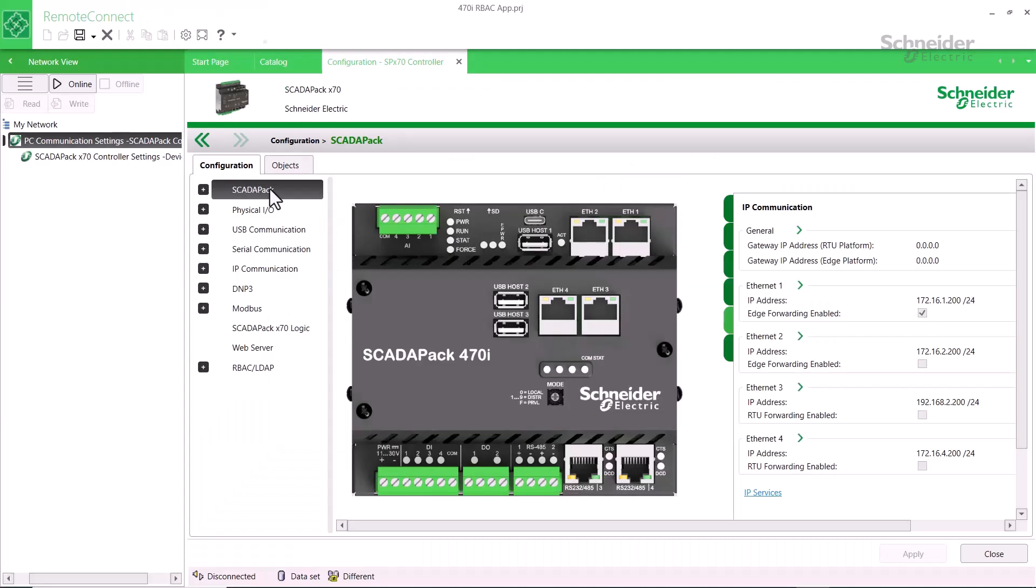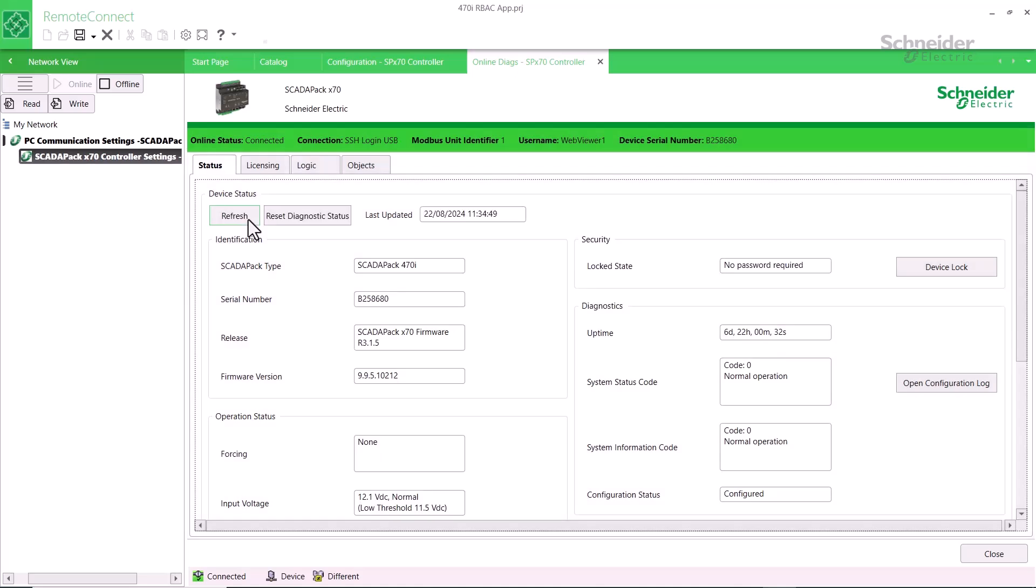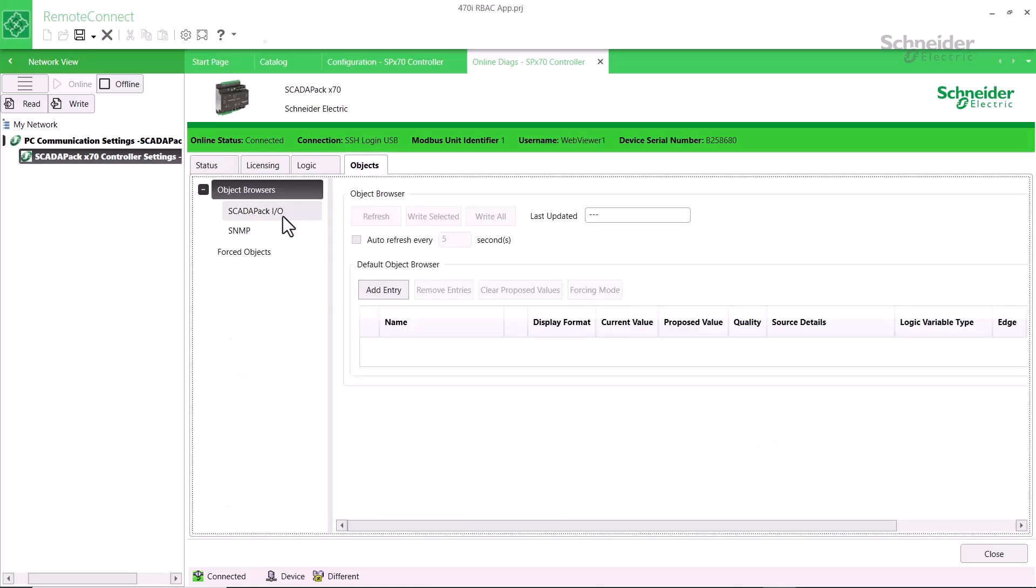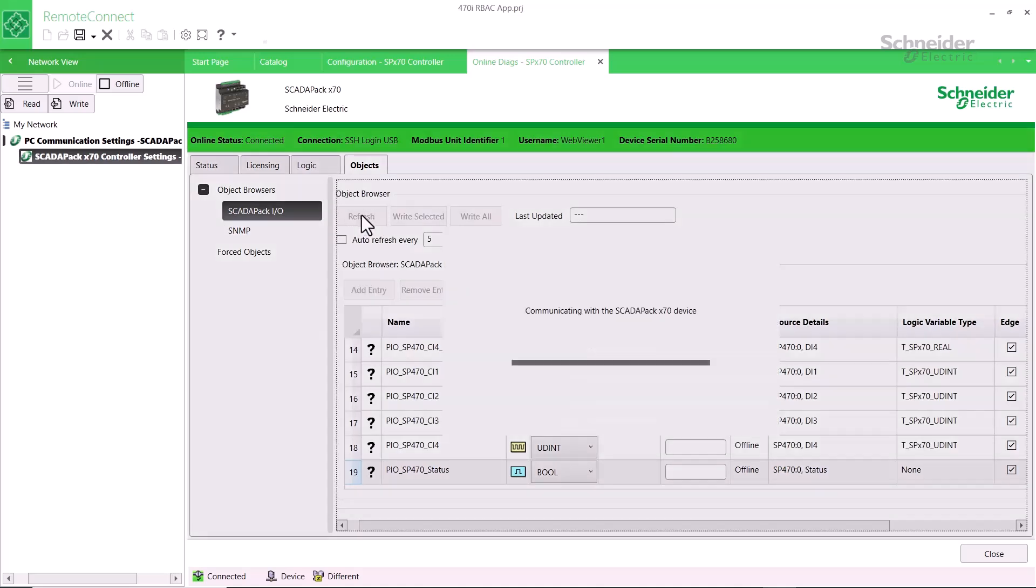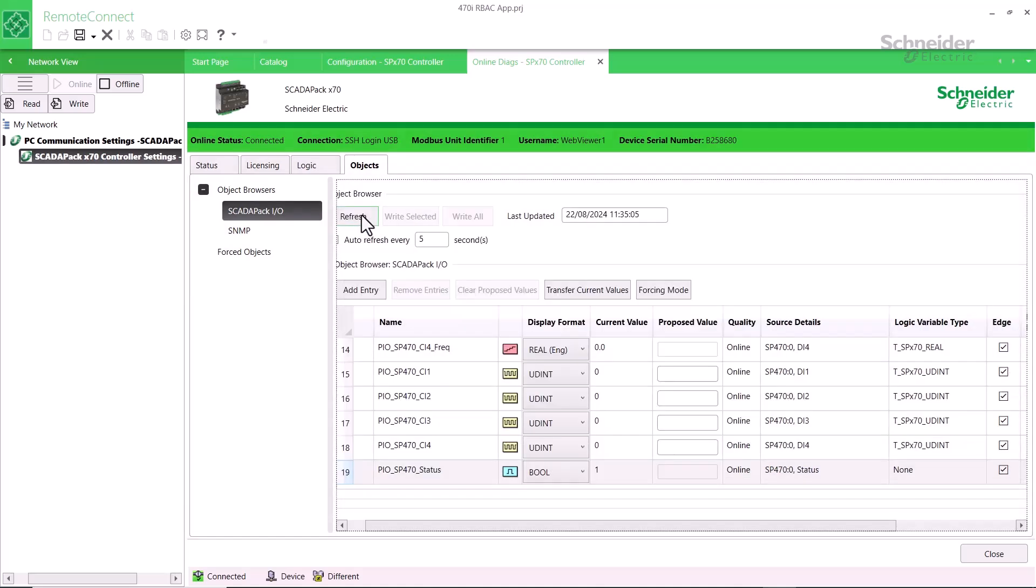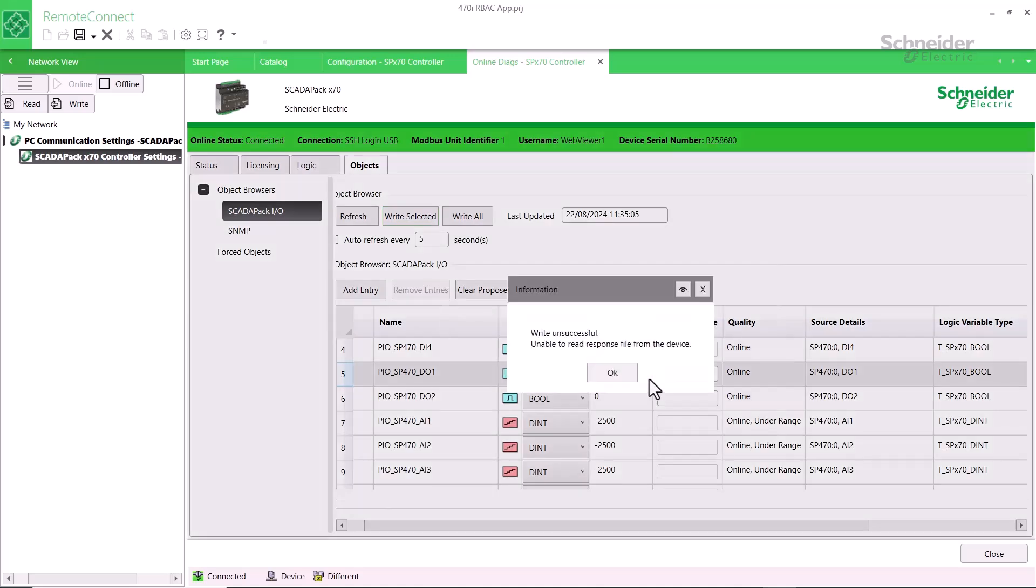To demonstrate how being assigned to specific roles will affect a user, we'll first log in to Remote Connect as WebViewer1. One of the rights provided to a WebViewer is the ability to use a browser to read object values. However this user is not allowed to write to an object. You can see that this operation is not allowed.